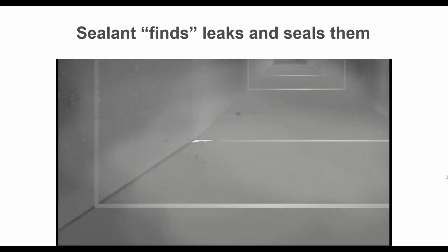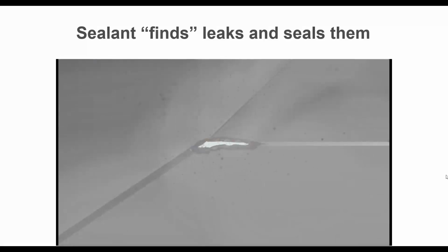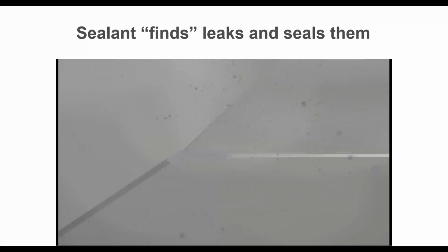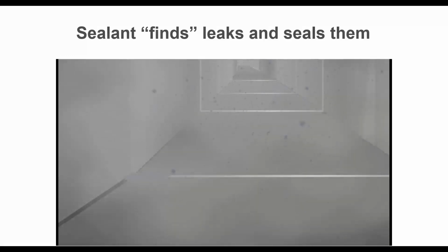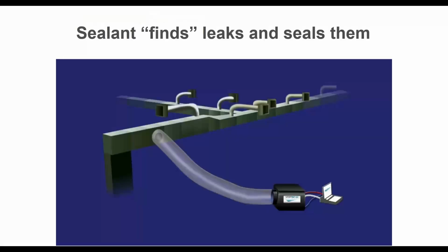When they come up to a crack, they go from high pressure in the duct to low pressure outside the duct, and it starts scabbing that hole closed. And then they're available. Whatever's coming down the duct now no longer wastes time there. It spends more time moving down the duct to the next crack that it finds. And there's thousands of these cracks all over, and it's just constantly moving down the duct system.